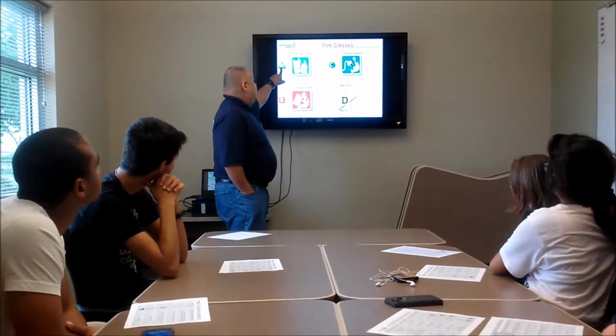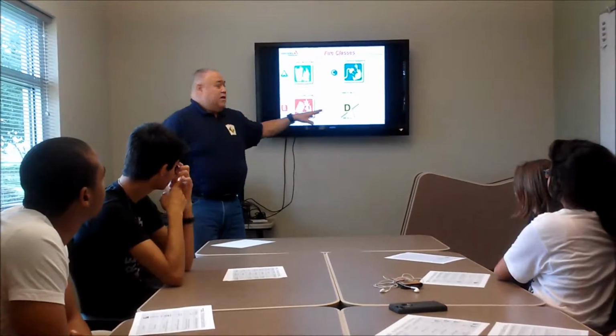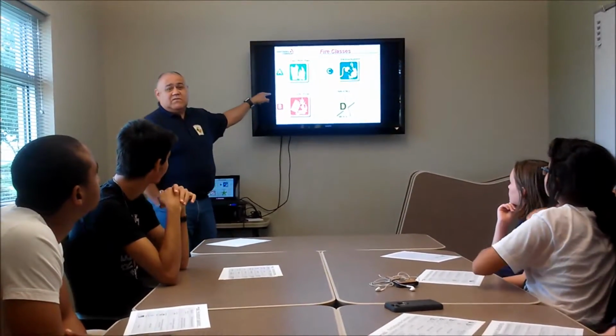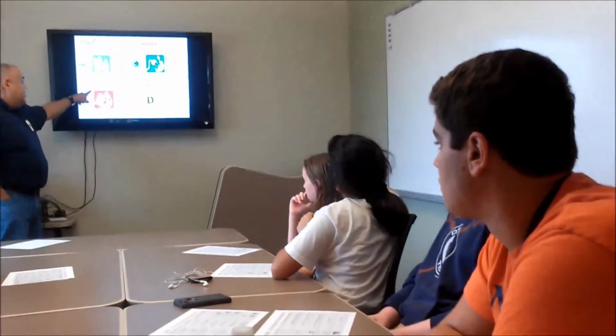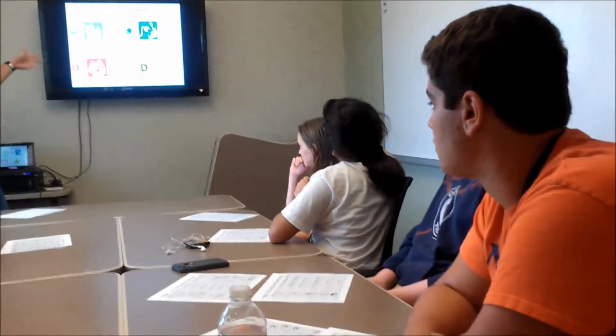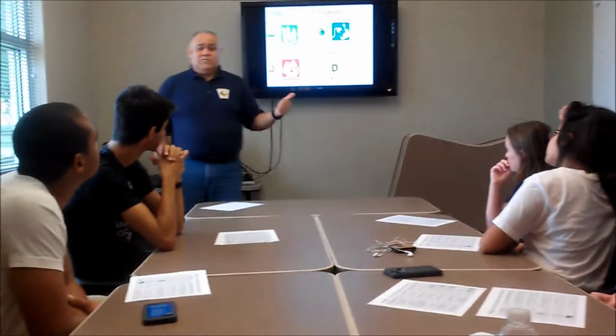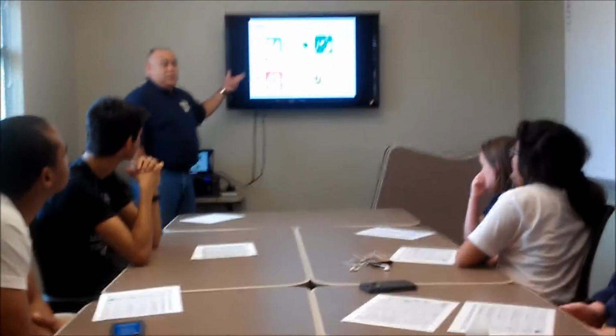These are the fire classes, and I'm going to teach you a really simple way to remember them. Class A: anything that's trash, wood, cloth, paper, rubber, many plastics. Think of it this way: an A-type fire is anything that produces ash. Type B is liquid, grease, or gasoline, oil, tar, oil-based paint, lacquers, flammable gases. Anything that boils is a class B. So again, A, ash; B, boils.